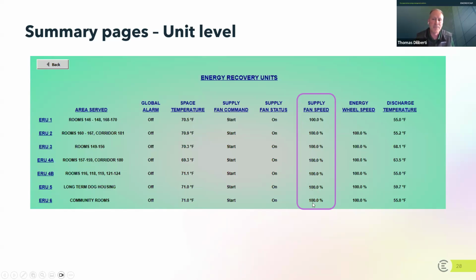Sometimes what this means is people have given up on the energy recovery units and they just program them in a simple way. And along the same line, one of the things that's confusing when looking at building automation systems is programming can happen at a couple different levels. You can have programming in the building automation system, but these variable frequency drives that are running at 100% have their own programming. And so sometimes there's conflict between the device in the field and the building automation system. And so I can't say for sure. I don't know whether there's a problem with the building automation system or something actually in the field. All I'm saying is this is something that's worth highlighting and tracking down because it is not intended to be that way. The whole point of having the fans, once again, is to run at speeds less than 100%.